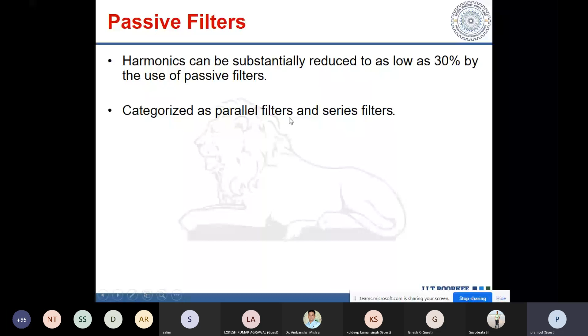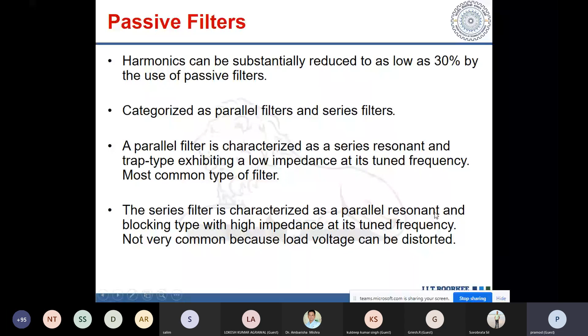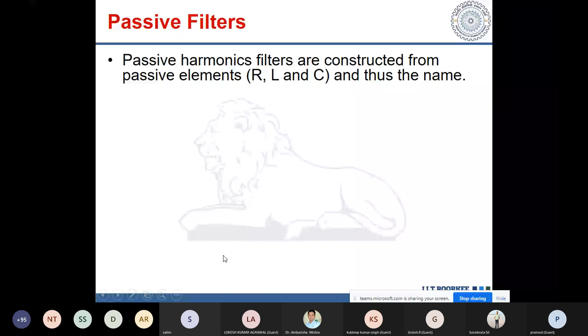A filter which is put in parallel with the load has series L and C, and the filter which is put in series with the load has parallel L and C. See the difference. A parallel filter is characterized as a series resonant trap type exhibiting low impedance at its tuned frequency. Mostly we use the parallel filter. The series filter is characterized as a parallel resonant blocking type with high impedance at its tuned frequency. These are made of R, L, and C, and that's why it is called a passive filter. Tuned series LC filters are mostly common.